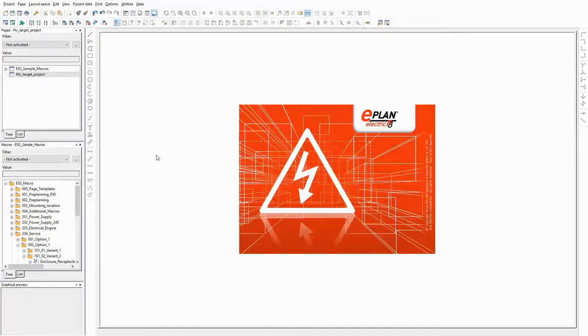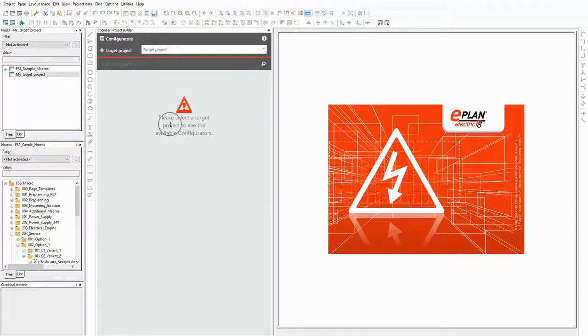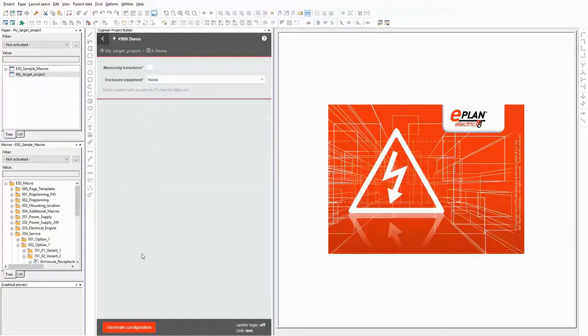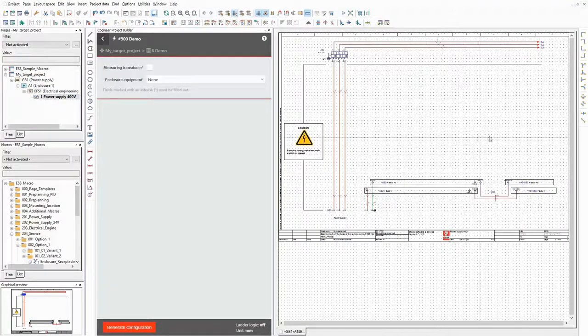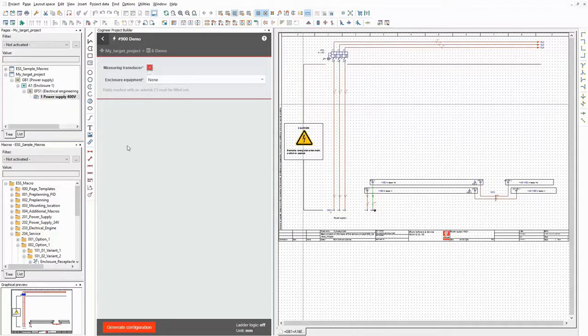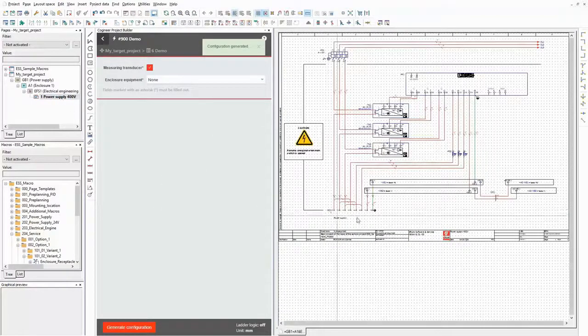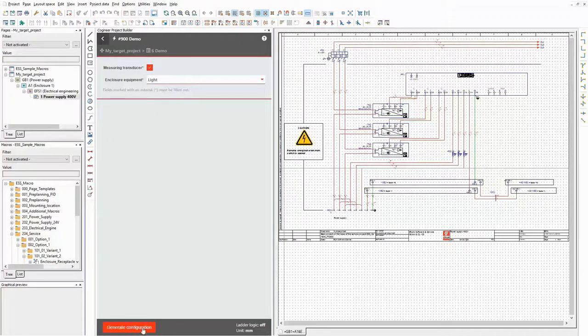In this part of the video I want to check if all variants are generated as planned. For bigger projects, it's easier to open the project builder on a second display and to check the conditions immediately when setting them up. First, I select the target project I want to generate in, then I open the configurator that contains the typical group I want to configure. The first variant should contain only the basic power supply without any additional options. The result is correct: the measuring transducer is not used and the enclosure equipment isn't available. Now I want to have the measuring transducer in the power supply but still no enclosure equipment. And the result is correct too. As you can see, the single wires for the power supply of the enclosure equipment are only used if there is any enclosure equipment.